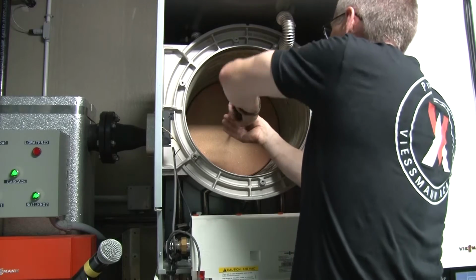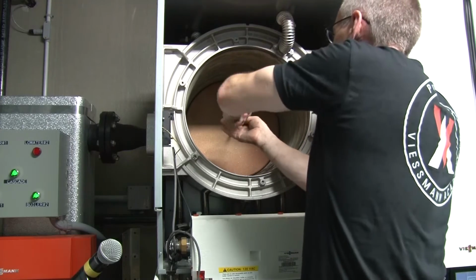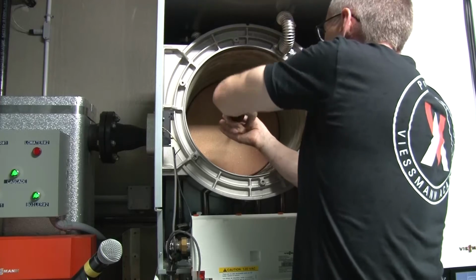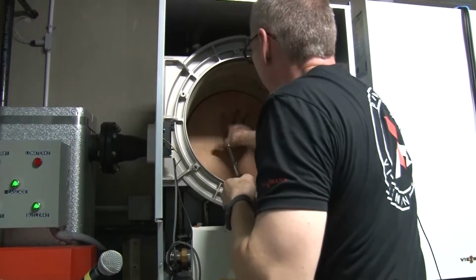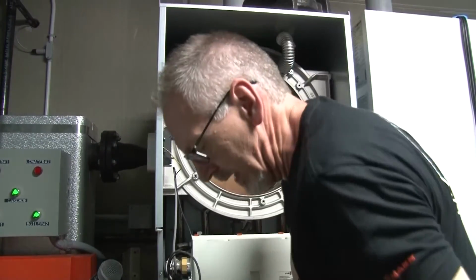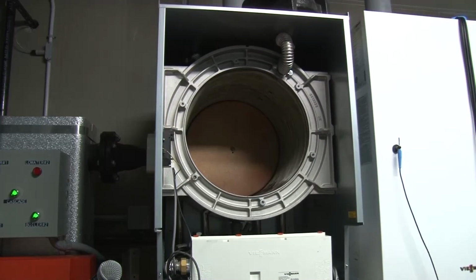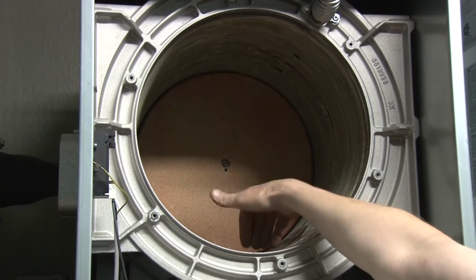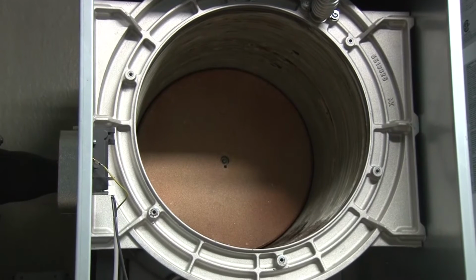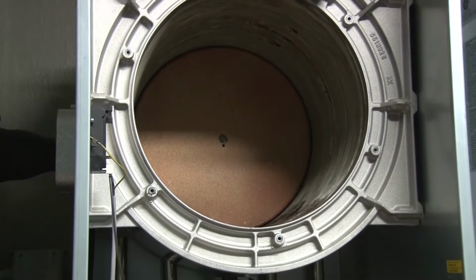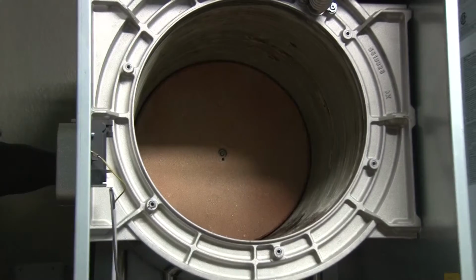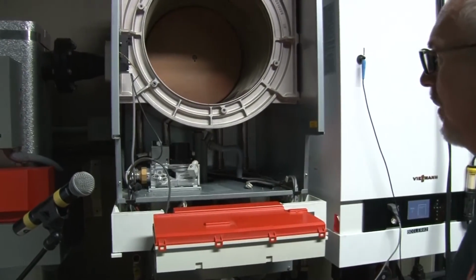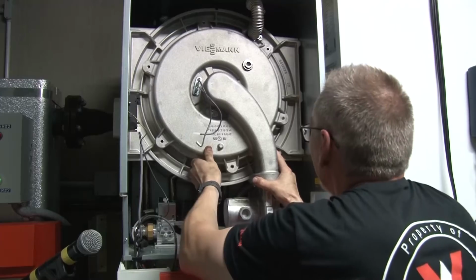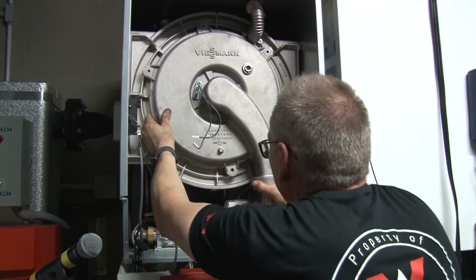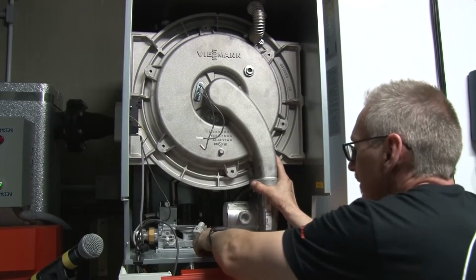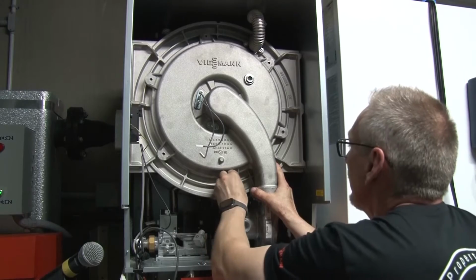Alright, so once we get this little bolt torqued down here, the washer does the tightening there. It will move, that's natural, it's just protecting that back wall. I'm going to hit this with a little bit of vacuum, but the important thing is these gaps in here, get that flue gas passageways opened up. And if you do that, then you're successful as far as getting your boiler up and running. So let's get that burner on. The height creates a bit of a challenge, but we will persevere.